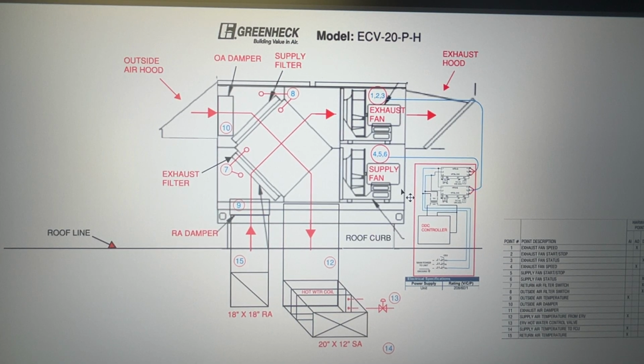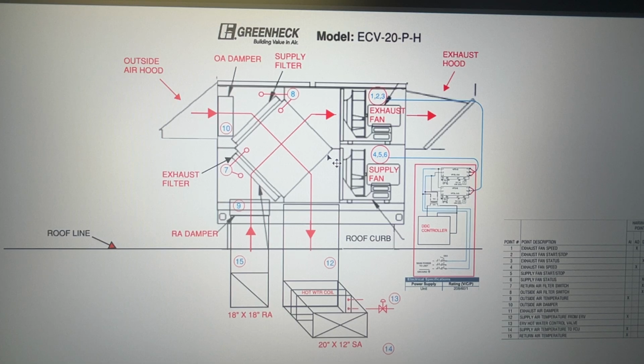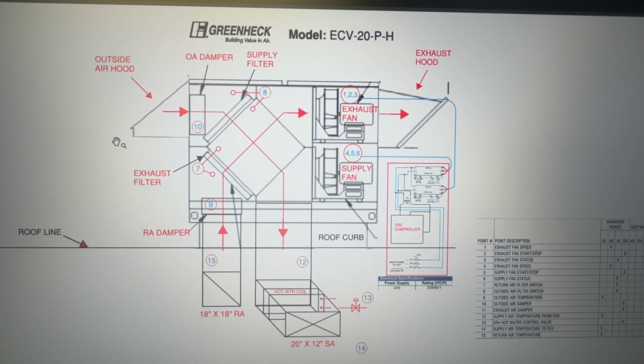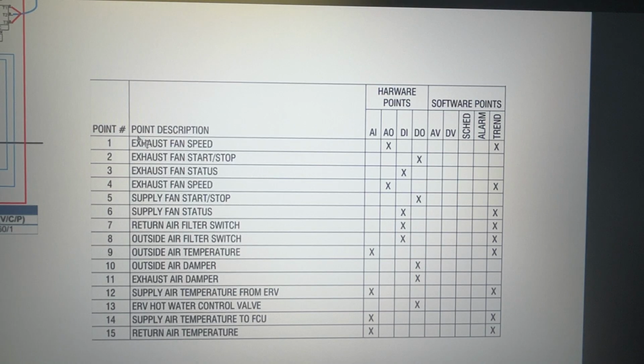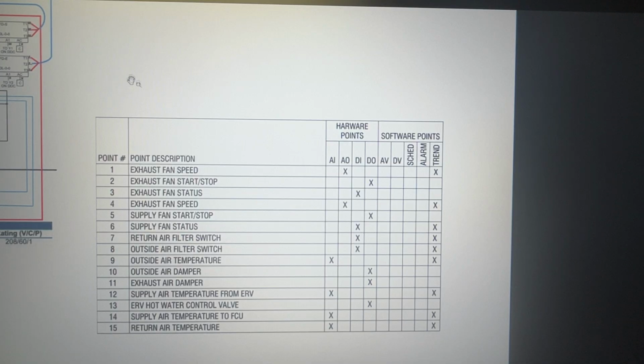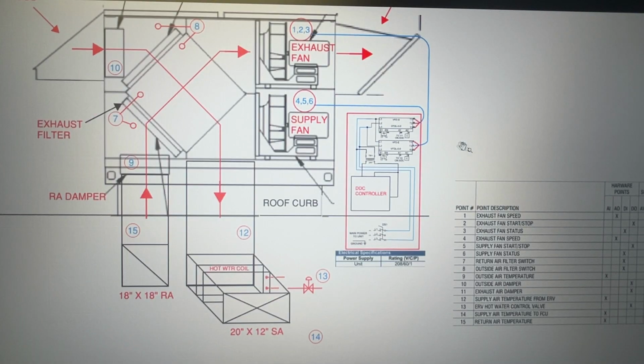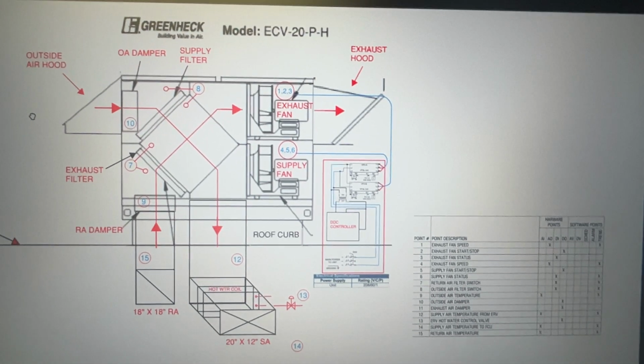So we've talked about how it works, but now I will talk about the controls of what goes into making it operate properly. On the control portion of this, there are points in several spaces that I have here in circles with numbers. So we have a legend over here. This legend shows all the points that are within that system in order for it to be controlled properly. So obviously we've got the 15 points here. So what I did is I reflected where they go within the ERV itself.